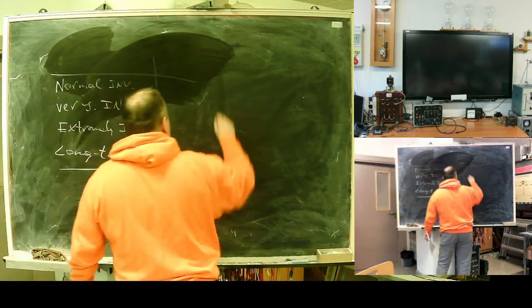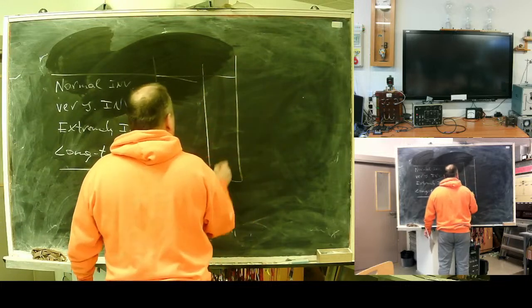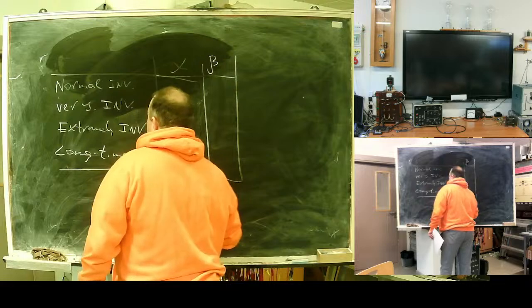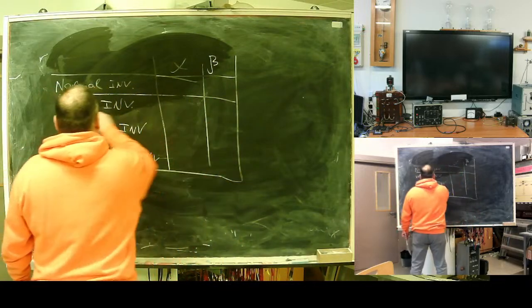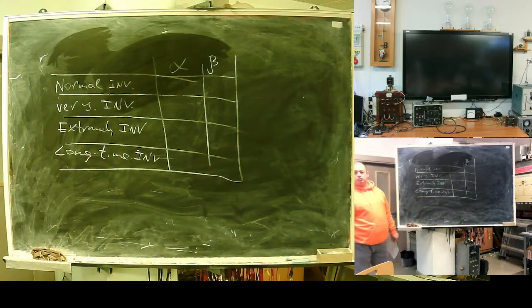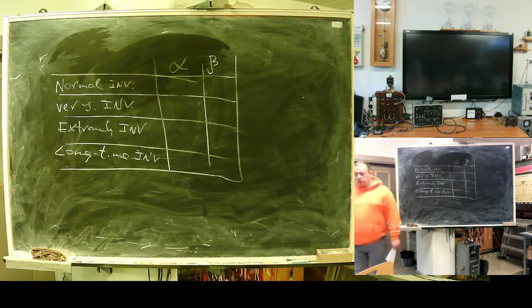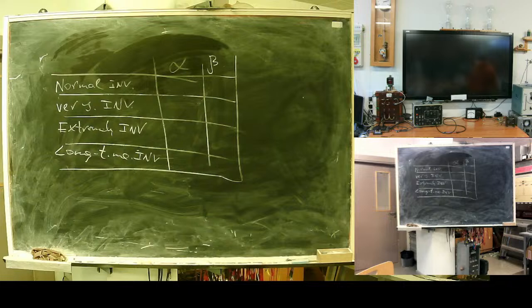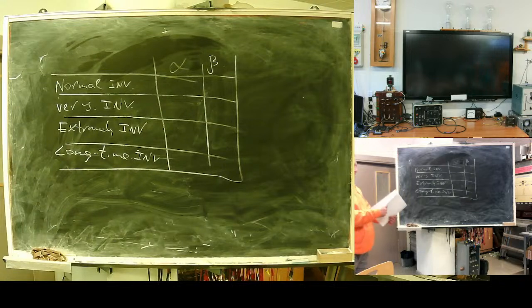For these characteristics you have an alpha and beta. In the standard, you can play with the time multiplier. The time multiplier allows you to shift characteristics, but the basic shape needs to correspond. Old school people have them on transparent paper and just find the best fit. In modern days, you can use a spreadsheet like Excel and create your own set of characteristics.